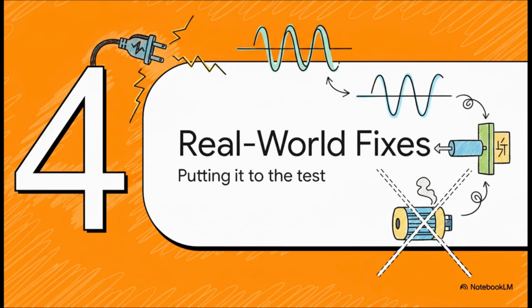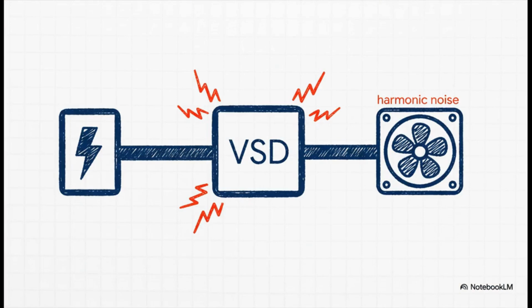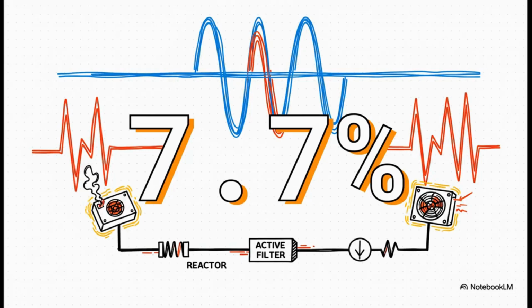Theory is one thing, but let's see how this stuff actually works out in the real world. We're going to look at a super common industrial setup and see just how effective these fixes can be. So here's our setup. A standard 400-volt system that's powering a 150-kilowatt variable speed drive. You know, the kind of thing you'd find running HVAC systems or big industrial pumps. This is a classic source of harmonics. And no surprise, when we hook up the meter, we find the total harmonic distortion, or THD, is sitting at 7.7%. Now, most standards say you need to be under 5%, so this system is officially non-compliant. It's polluting the grid, and it's stressing out its own parts.